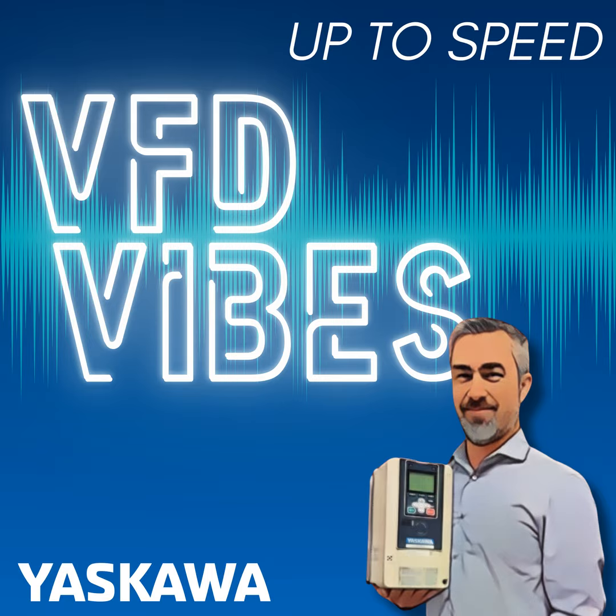Well, I think we have to talk about the difference between grounding and bonding to start. In a previous discussion, we talked about power system grounding, and this is commonly referred to as system grounding. What grounding or earthing means is to somehow connect something to the earth, literally the planet Earth. And one of the little lies we tell ourselves is that the surface of the Earth is an equal potential surface, meaning that if I were to measure the voltage anywhere on the surface of the Earth with respect to any other point on the surface of the Earth, I would see zero, which of course is not true because Earth has an impedance. But anyway, we talk about connecting something to the earth. The idea is that someone's standing on the earth, if they were to touch anything connected to the earth electrically, they're not going to get a shock.